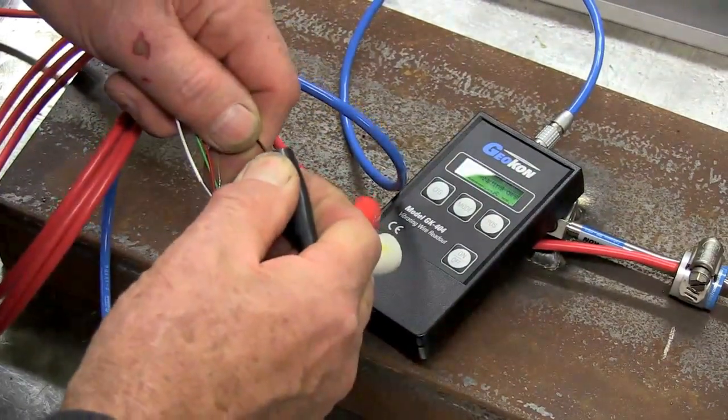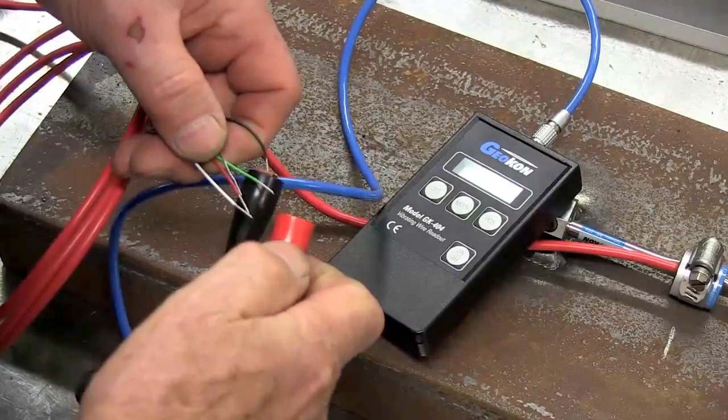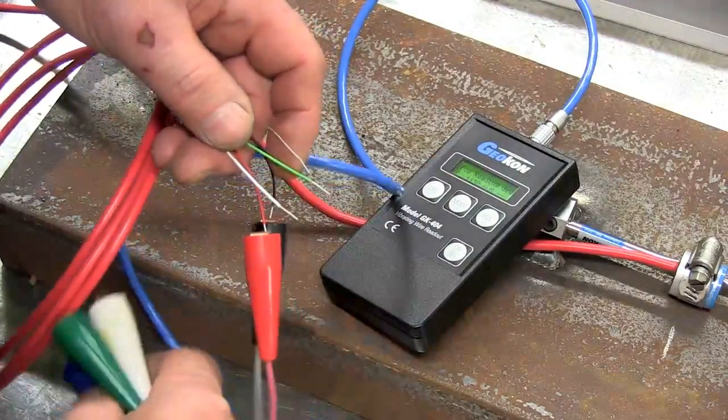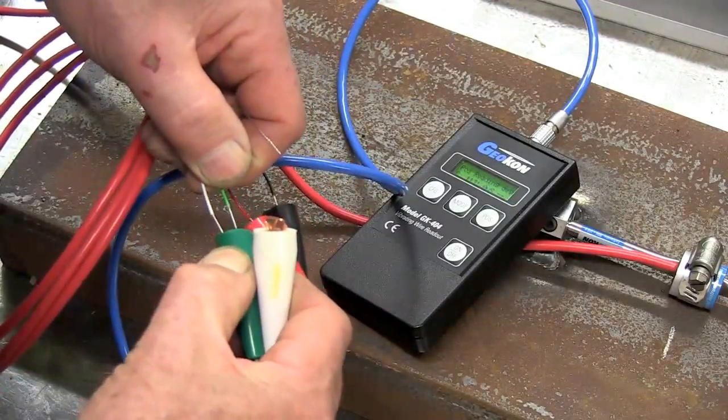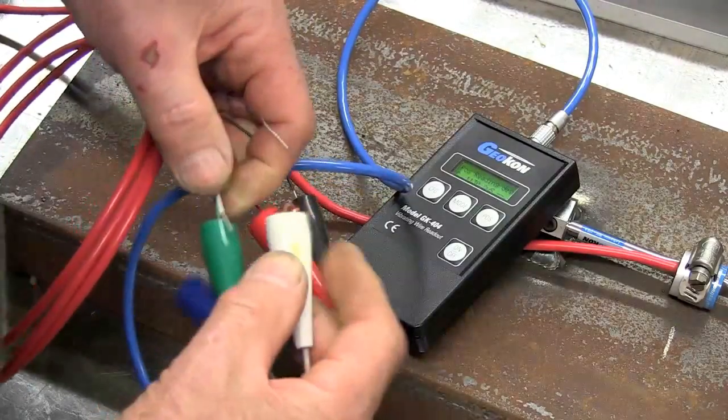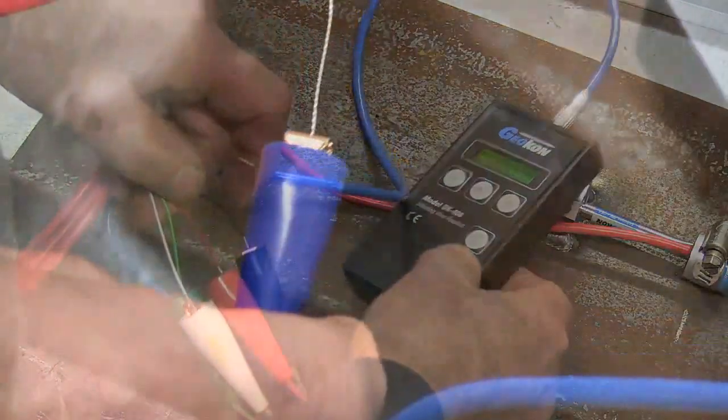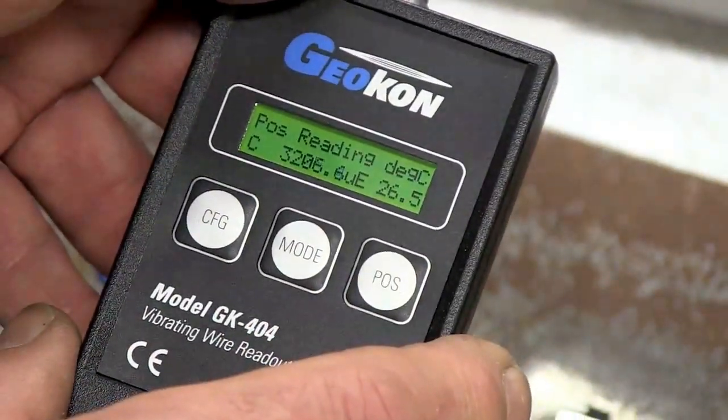The black and the red are connected to the strain gauge itself. The green and the white are for a temperature gauge. It's included in that thermistor for measuring temperature. We always take simultaneous readings of strain and temperatures. The blue wire is for elimination of electrical noise.